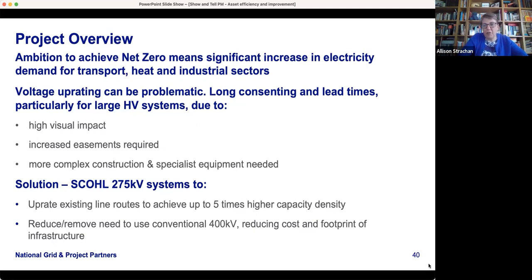Unfortunately, that can be problematic, because going to higher voltages can mean potentially long consenting times and long lead times for these projects, since higher voltage means higher visual impact. The towers are bigger, there's a bigger width of corridor required for the technology, and the construction can be more complex and require more specialist equipment.